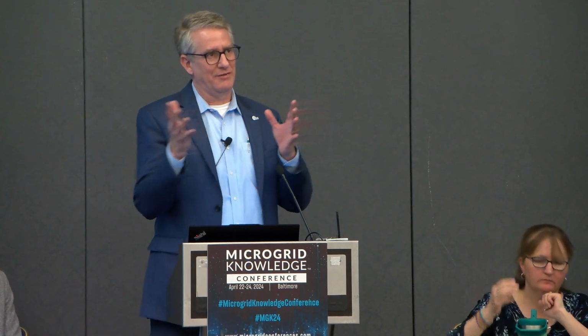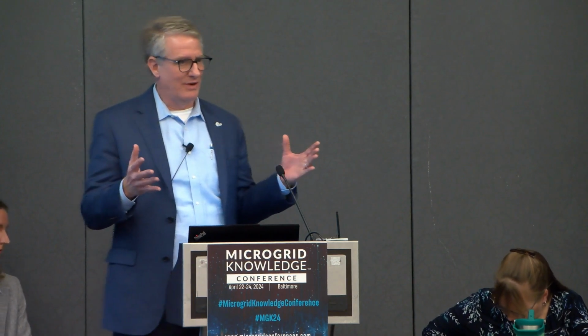On the 5CP case, we're looking to hit just 1 hour of peak basically in the day, so having that extra cushion is good. Even if a 4-hour battery decays to 75%, beyond that it would crash very rapidly—but at that stage we'd still have 3 hours of duration, so we should be able to cover a 1-hour case. The frequency regulation follows in real time; we float the battery at 50% state of charge and let the market drive it up and down. So duration hasn't really been an issue.